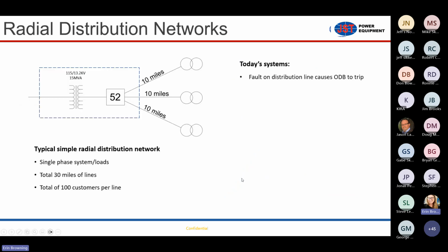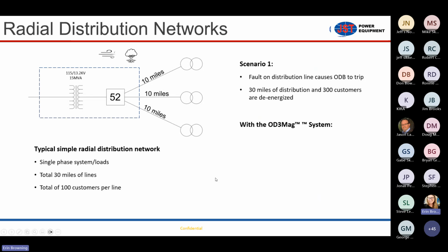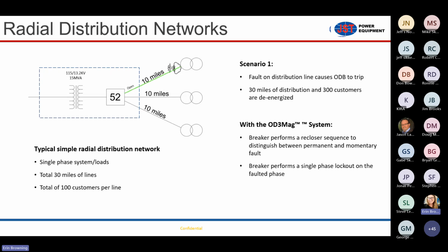To look at it a little bit more from an animation standpoint, again, I'm using a tree as just a general example. A tree hits the line in a typical breaker, all three phases are going to open, close, open, close, open, close, and then go into three-phase lockout if it's a permanent fault. But with the OD3Mag breaker, if that tree branch hits one line, only one line is going to open and close while the other two lines stay energized. So you're not affecting any of these guys from a momentary standpoint.